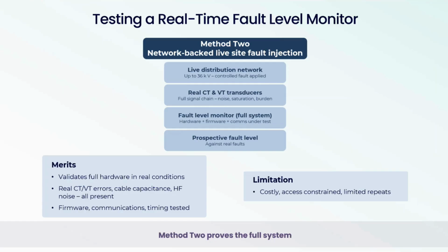If we go to the next slide. So to do this, we needed to find a live test network that had a representative fault level of an actual distribution network. It was quite difficult to find because on real distribution networks we can't just throw faults, because what we wanted to do was be able to throw a solid earth fault and measure the fault current and compare that to the predicted fault level from the real-time fault level monitor. There's a few outdoor test networks in the UK, but they weren't suitable because they're not backed by an actual grid network. So we had to go further afield.